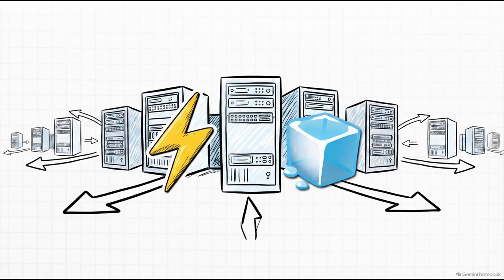Now, what's really interesting about this is that your physical rack layout can actually dictate your SCC sizing. It's like a giant puzzle. You might have the exact same number of system nodes, but if you choose to spread them out sparsely across, say, several hundred racks, rather than fully populating just a few racks, you are dramatically increasing the number of power distribution units and cooling distribution units that need monitoring. A wider physical footprint literally means a heavier telemetry load on your SCC, even if your actual server count hasn't changed one bit.